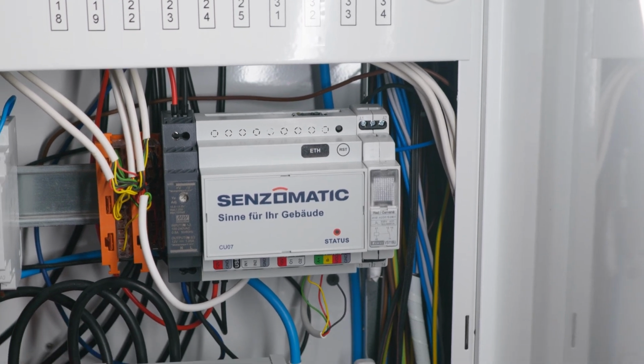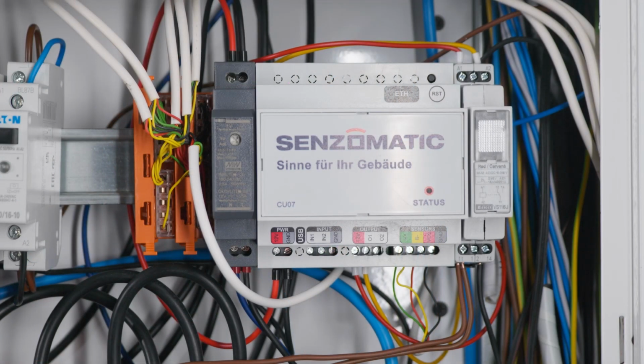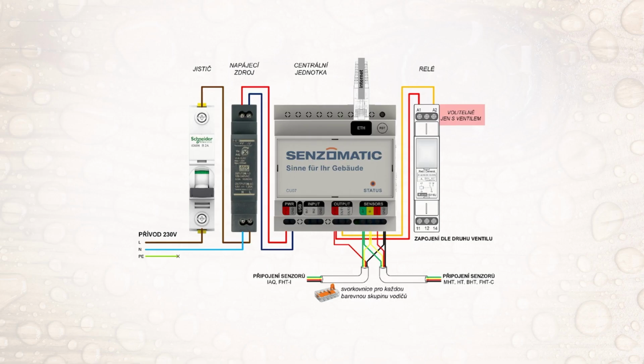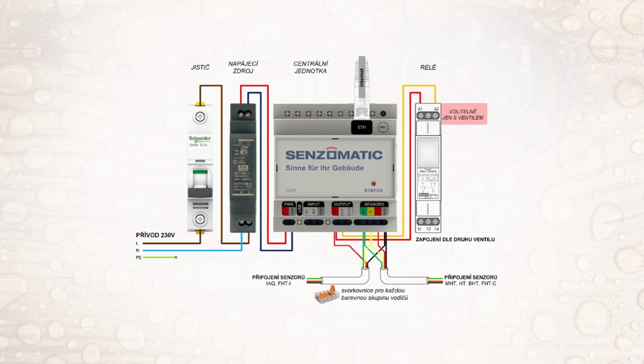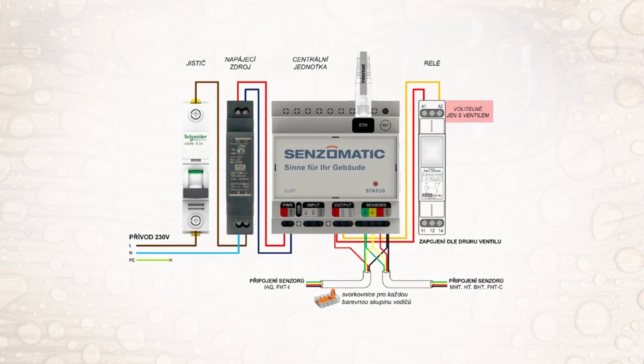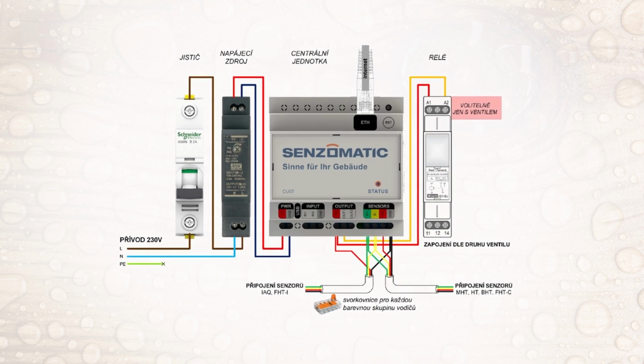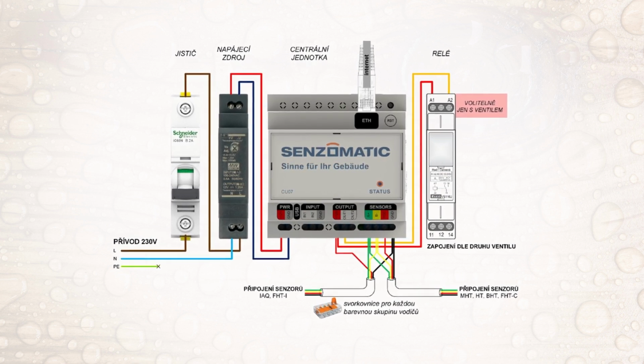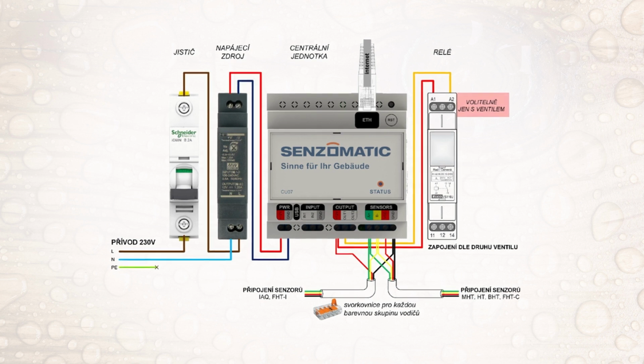Connect the signal relay from the central unit to the control terminals from the terminals marked A1 and A2 as shown in the diagram. In the supplied relay type, the signal wires are connected from above. On the bottom of the relay, you'll find terminals for switching the control wire for the valve. Connect the valve according to the attached diagram. Connect the phase wire through a separate circuit breaker. Connect the neutral wire to the correct circuit. Connect the valve control wire to the relay.